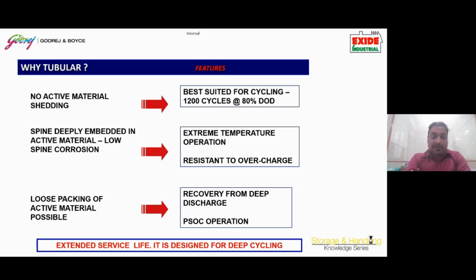Tubular batteries have another property: they can even be recovered from a deep discharge state. So if today your battery is discharged due to some operational condition, beyond 80% or even up to 80%, if you don't prolong the period before recharge, these batteries can very well be recovered from a state of deep discharge. While the flat pasted positive batteries, once they go into a deep discharge state, are very difficult to revive. So we always recommend that the end cutoff voltage setting of the batteries should be designed and maintained properly, and it should be ensured that the batteries do not discharge beyond that point.